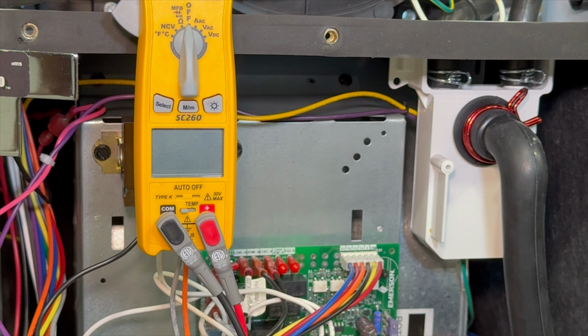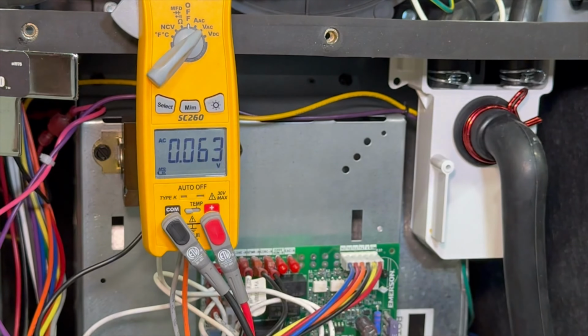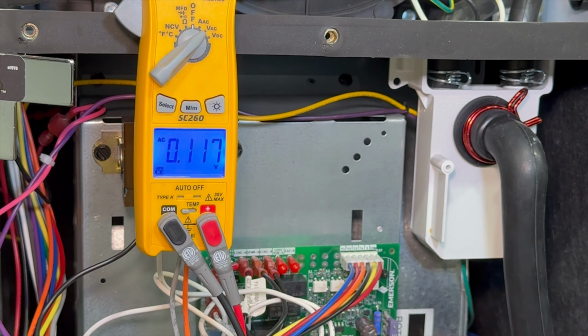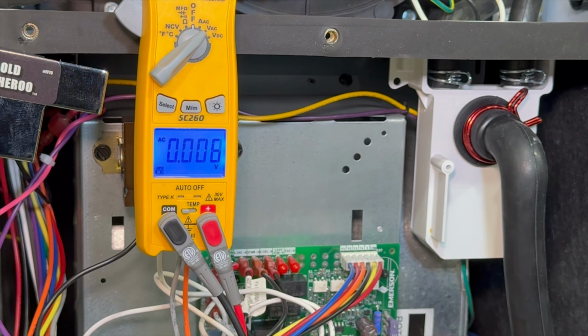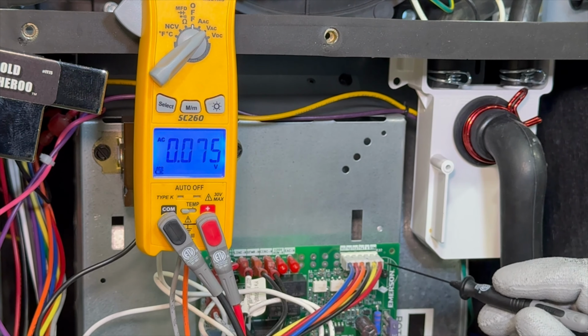Now, for this particular furnace, we're going to use the same manufacturer with a different model, and we're going to also check our communicating voltages, because we're talking about a constant torque ECM, but remember, not all constant torque ECMs use the same type of voltage. When we looked at our previous model, we had a DC voltage. So this time, we're going to check both. We're going to turn power on to the unit, set our meter to volts AC to begin the process, and check the voltages from common to T1 again and see what we have.